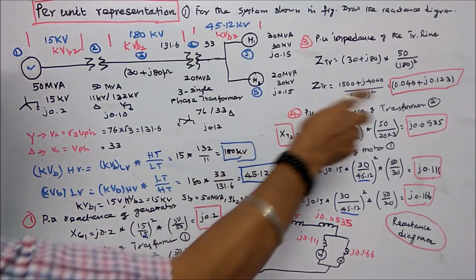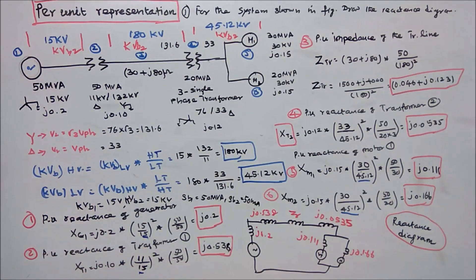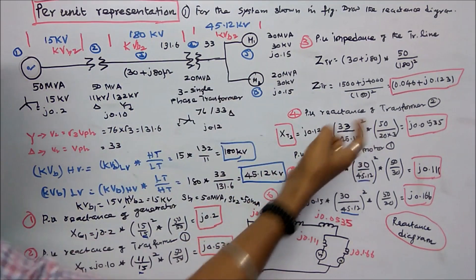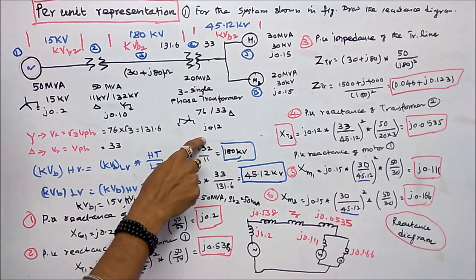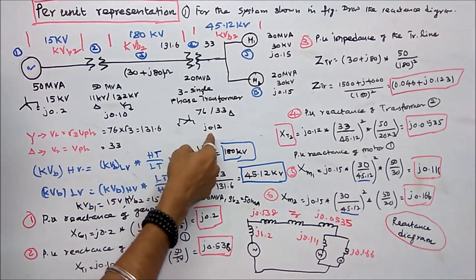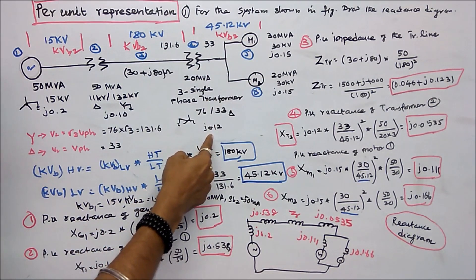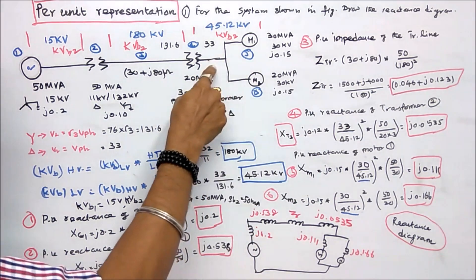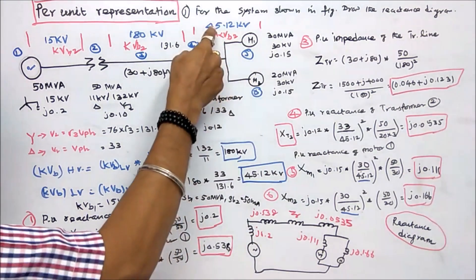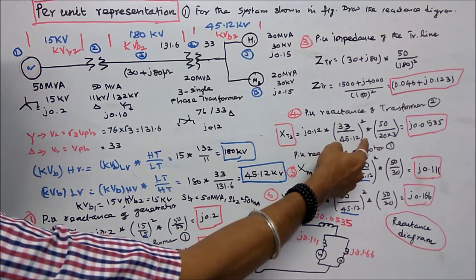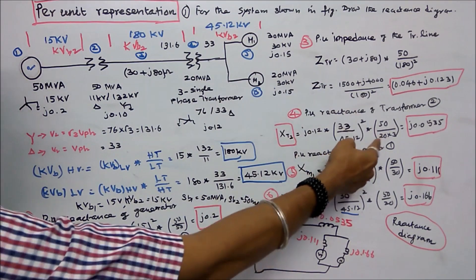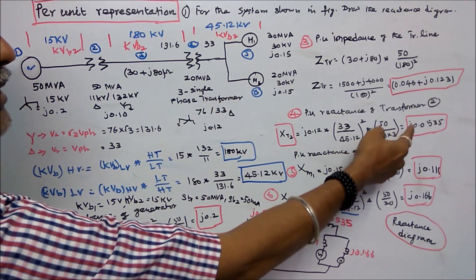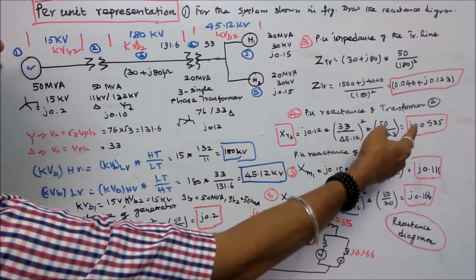Fourth is per unit reactance of the three-phase transformer bank. Three transformers, 3 times 20 equals 60 MVA total. Actual leakage reactance of the whole setup is J0.12. Per unit equals J0.12 into (33/45.12) squared times 50/60, where 60 is 20 times 3. That equals J0.0535.